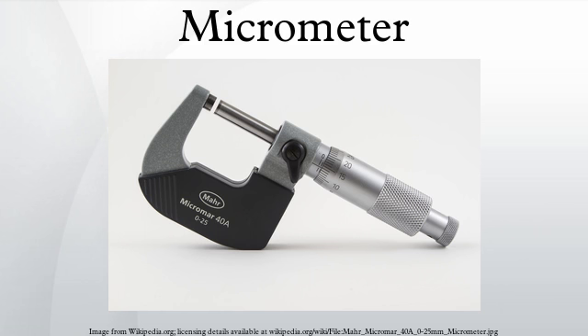Dirt, abuse, and low operator skill are the main sources of error. The accuracy of micrometers is checked by using them to measure gauge blocks, rods, or similar standards whose lengths are precisely and accurately known. If the gauge block is known to be 0.7500 inches plus or minus .00005, then the micrometer should measure it as 0.7500. If the micrometer measures 0.7503 inches, then it is out of calibration.